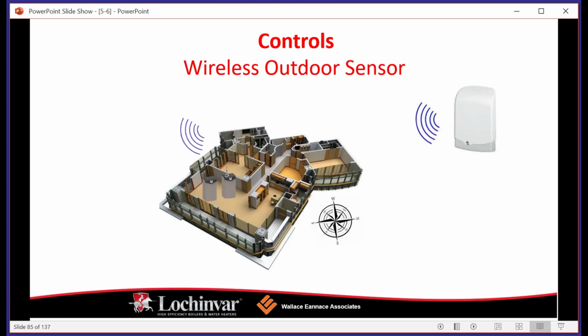So when we talk about an outdoor air sensor, it is included with all of the boilers that you're going to buy. The advantage of an outdoor air sensor is you can hook this up and you can tell the boiler essentially what the temperature of the outdoor air is. The advantage of this is that it allows the boiler to really maximize its modulation and its turn down.